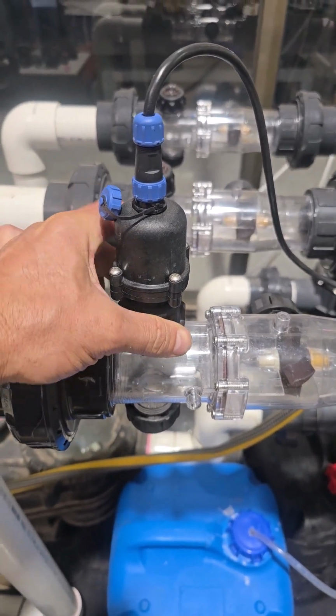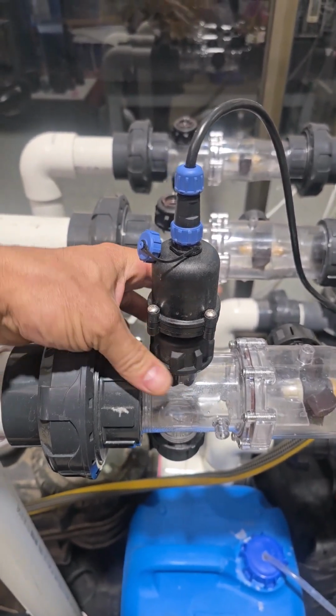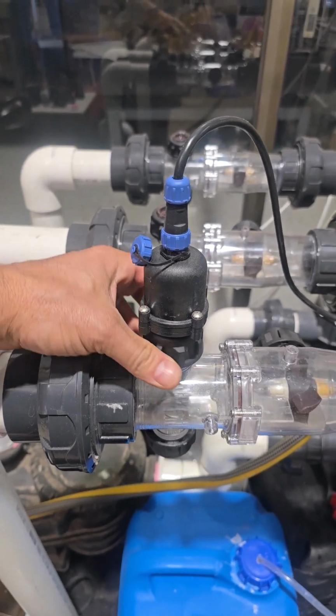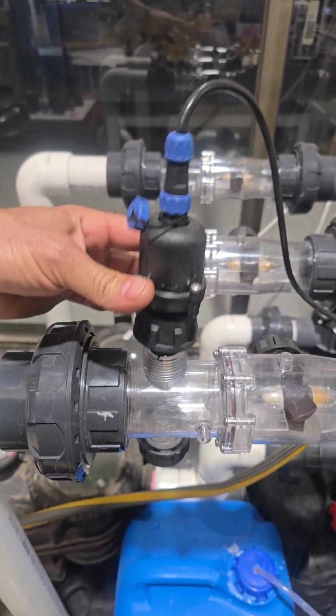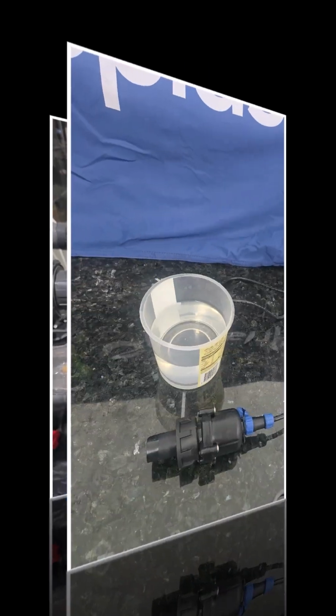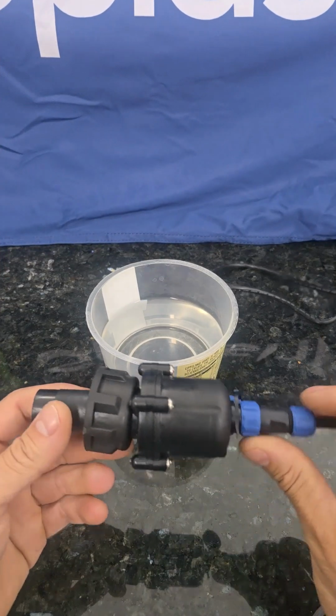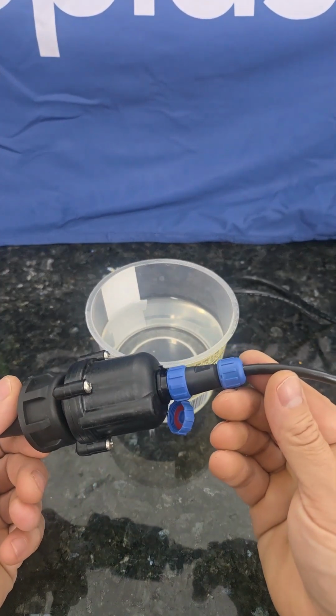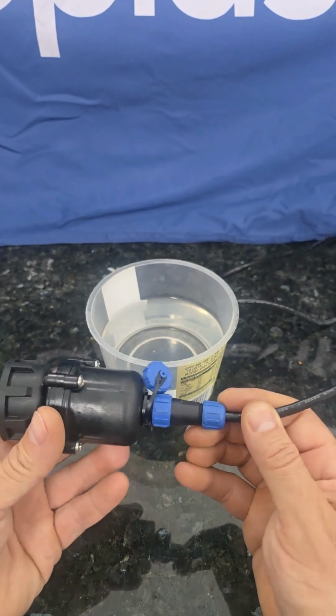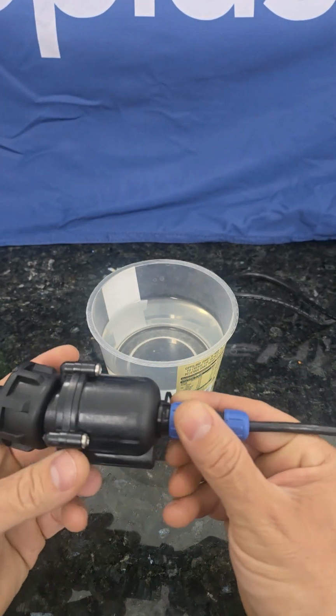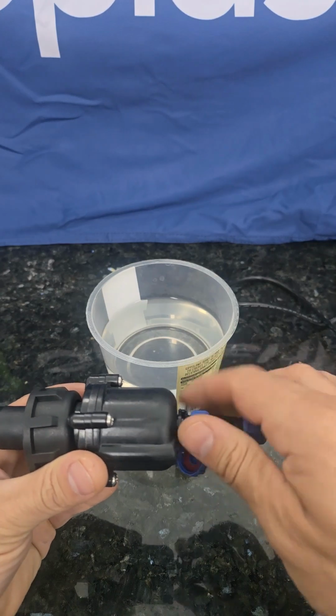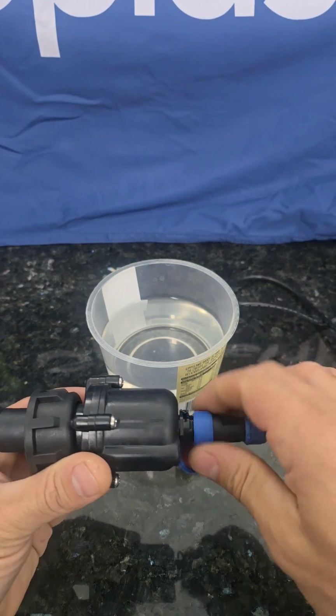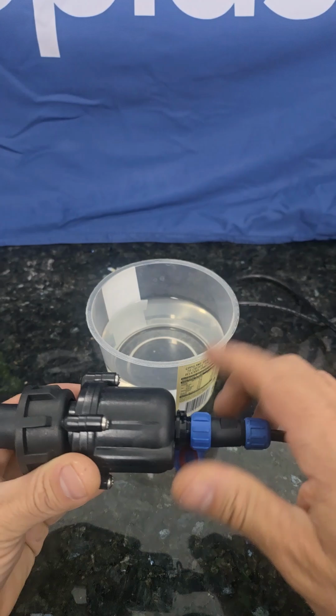Next, loosen the nut at the base of the multi-probe in an anti-clockwise direction. Once completely undone, you will be able to pull the multi-probe out of the flow sensor housing. You also have the option of removing the cable in case you want to do this on a bench. Unscrew the blue nut in an anti-clockwise direction until loose. Then pull the plug away from the multi-probe.